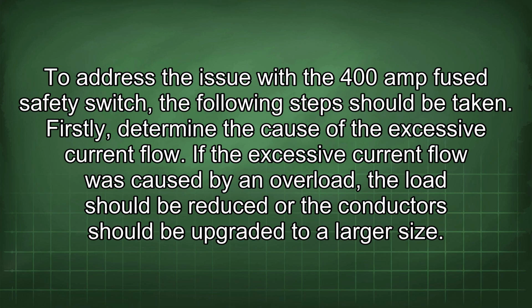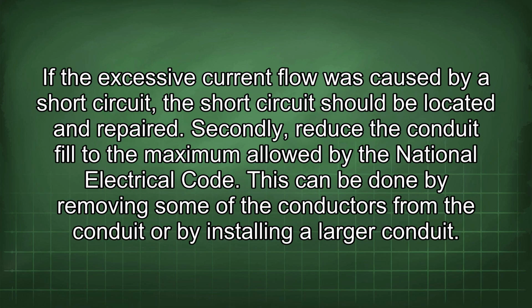If the excessive current flow was caused by an overload, the load should be reduced or the conductors should be upgraded to a larger size. If the excessive current flow was caused by a short circuit, the short circuit should be located and repaired. Secondly, reduce the conduit fill to the maximum allowed by the National Electrical Code. This can be done by removing some of the conductors from the conduit or by installing a larger conduit.